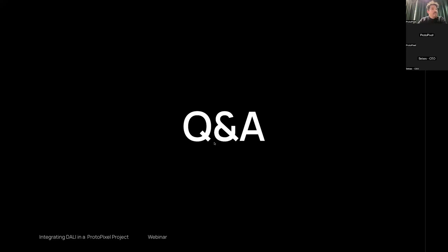First question: how many moods can be created, I guess, in the software suite? You say 16, like in DALI. So please, Kiks, if you take this one. Yes, you can create as many moods as you need, but we don't have a limitation on it. The only thing, of course, due to the limitations of the DALI technology, you will be able to create only 16 moods that are synchronous, that will change all together when they are applied. But you can create as many as you want, and then accelerate the other ones as you need.